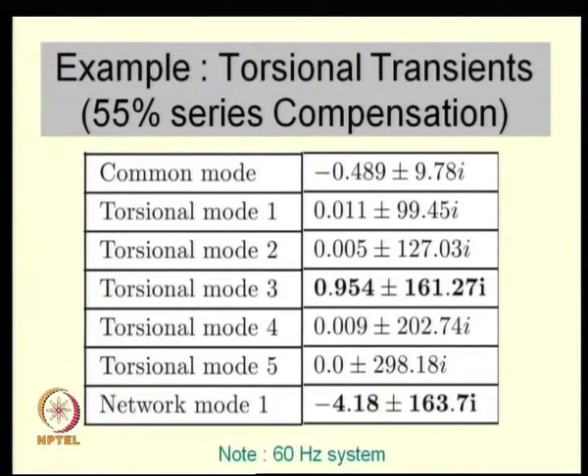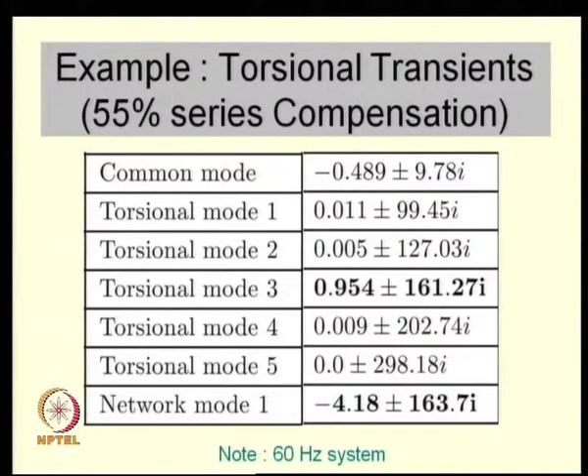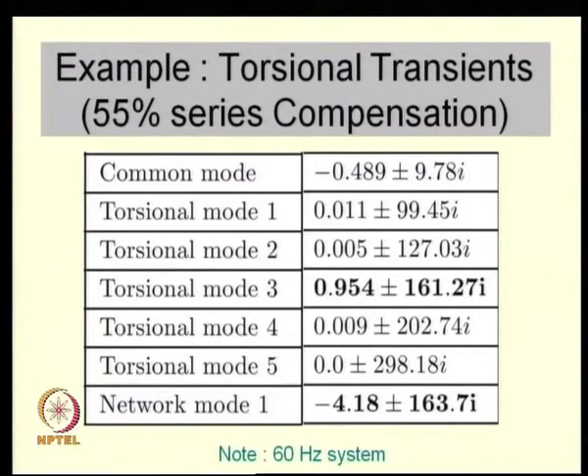In actual practice, there will be some viscous damping, and torsional modes 1, 2, 4, and 5 would be stable if viscous damping were considered. However, torsional mode 3 has a very large positive real part and could cause a real problem. This problem occurs when you have a sub-synchronous network mode due to series compensation, and the network mode frequency coincides with a torsional mode frequency.